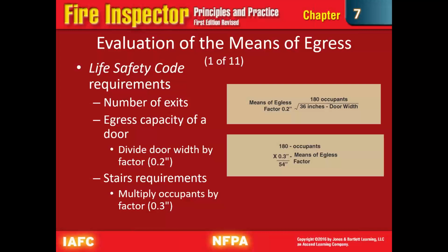All right, so say you have an occupancy load of 540 people, but whenever you calculate this and you evaluate your exit, by the size of the door, you can only evacuate 500 people out. Well, even though you have the space for 540, your exits don't support that, so you have to bring it down to meet that level.